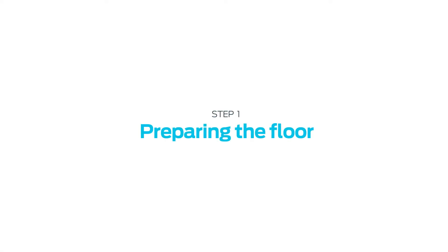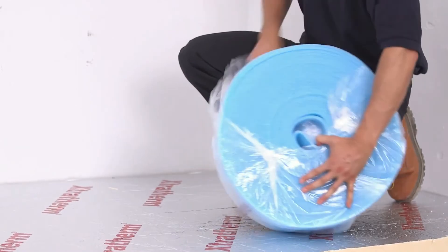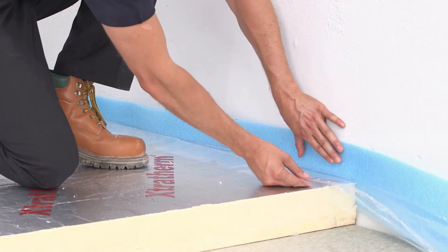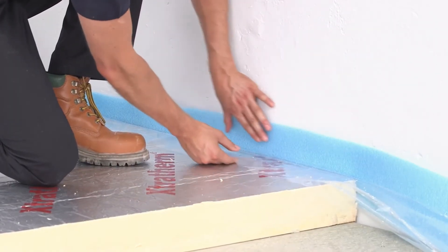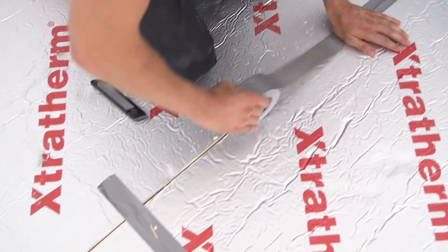Preparing the Floor. An expansion strip is required to accommodate expansion that occurs within the screed as a result of it heating up. This strip should be fitted around the room's perimeter and taped to the membrane. The joints must then be securely taped over.